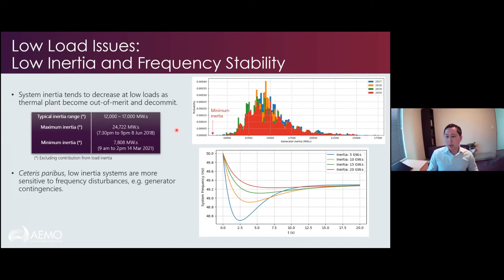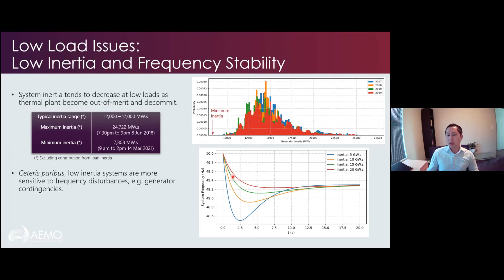And the point to make is that ceteris paribus, all things being equal, the lower the inertia, the more sensitive it is to frequency disturbances. So if you had a generator contingency, or a generator tripping, with everything else being equal, so let's say the primary frequency response and so forth is the same, then a small system, a 5 gigawatt second system, has a lot more frequency deviation than a 10, 15, or 20 gigawatt second system. So we're sitting around this area here, and as we get lower and lower, we are seeing more frequency stability sensitivities.